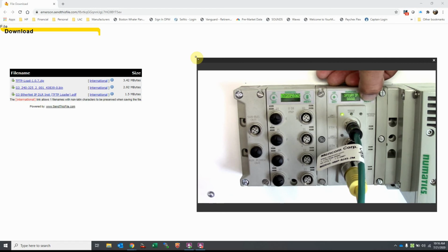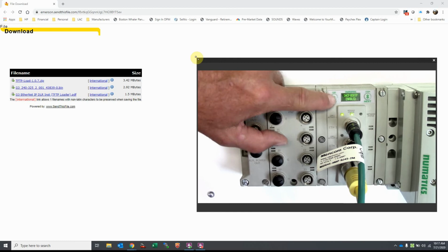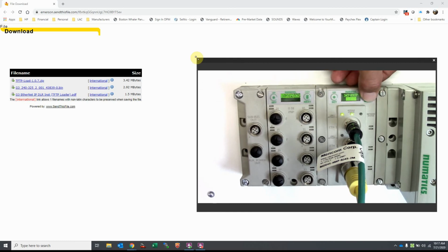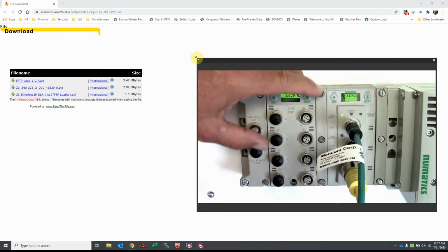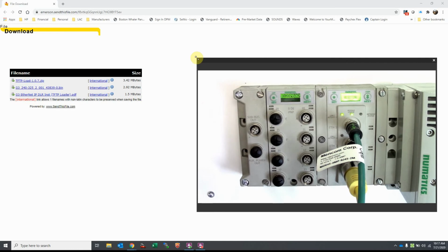We're going to select the next button until we get to DHCP BootP enable. We're going to press select, and that will highlight the word enabled, and we're going to move until we hit disable, hit set. We're going to accept that. What that does is now, instead of the node looking for the server to assign an IP address, it's going to have a static, very specific IP address. In this case, it's 192.168.3.90.